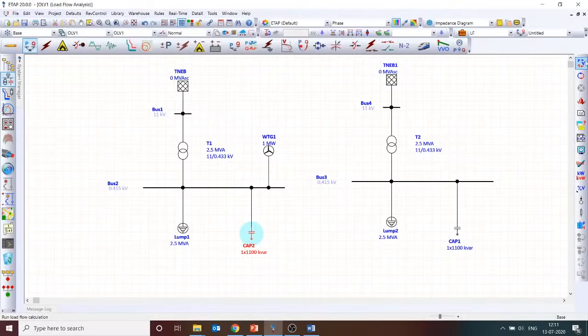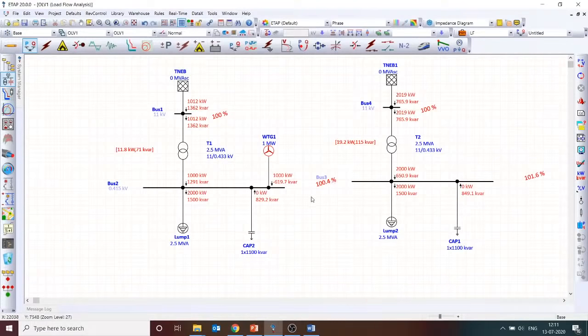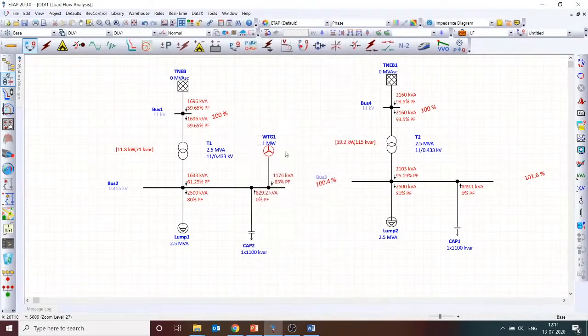Yes, perfect. Let me go ahead. Even after adding a capacitor bank with the wind turbine generator, I have compensated the reactive power requirements only for the loads. I have not compensated the reactive power requirements needed for the wind turbine generator. So the power factor is still low. Here I am able to maintain a 0.93 power factor where I don't have any penalty. But when I add a wind turbine generator, even with the existing capacitor, I need to pay a huge penalty because the power factor is still low. It is only 0.6 per unit.